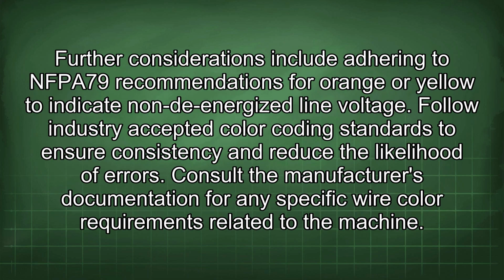Further considerations include adhering to NFPA 79 recommendations for orange or yellow to indicate non-de-energized line voltage. Follow industry-accepted color coding standards to ensure consistency and reduce the likelihood of errors. Consult the manufacturer's documentation for any specific wire color requirements related to the machine.